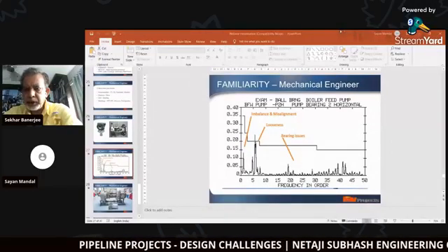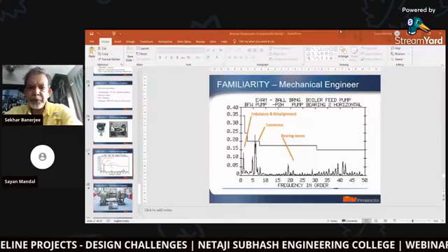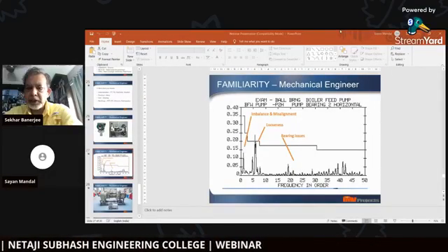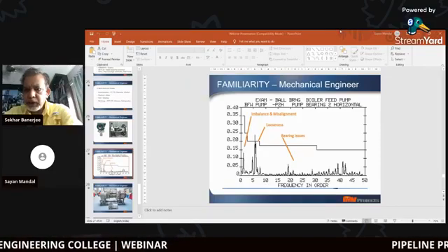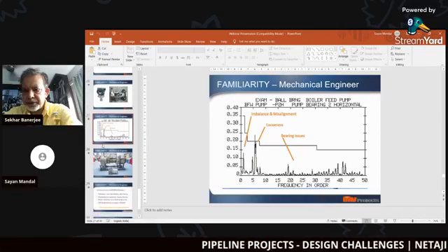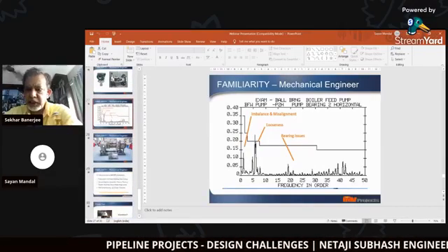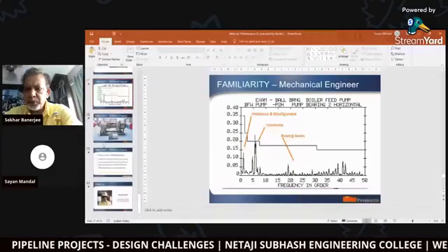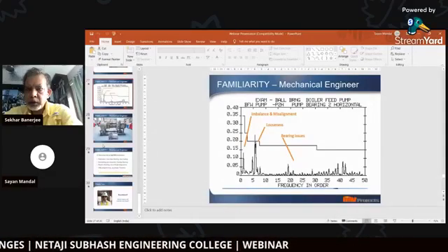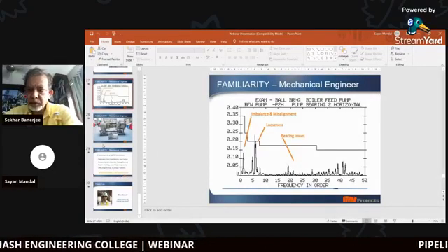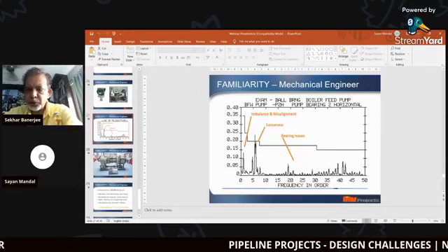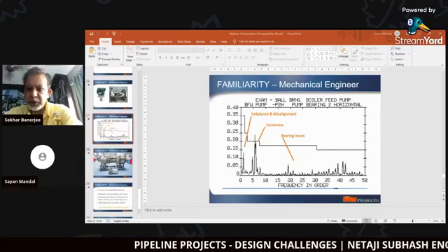This 5 means 5 times the RPM of the pump. So if, say, the pump is spinning at 1500 RPM, this frequency is 7500. 10 is like that, 15,000. We can get a complete frequency reading here. Based on the complete frequency reading, now we start finding out which one is going wrong. So for instance, for this reading, you can see the first one is for imbalance and misalignment between 1 and 2, basically, for imbalance and misalignment.